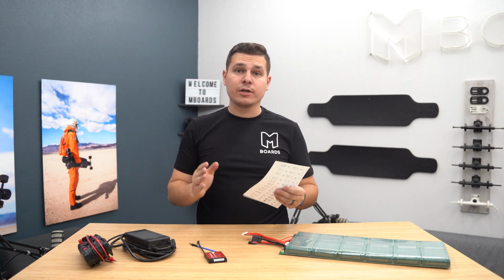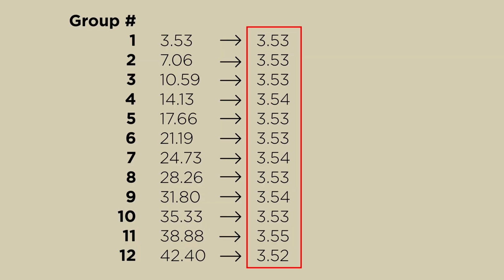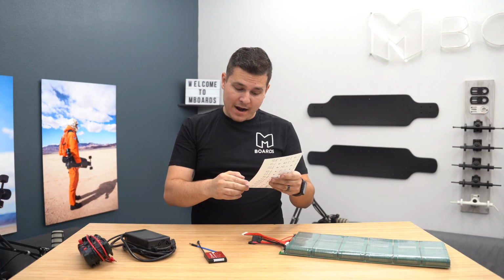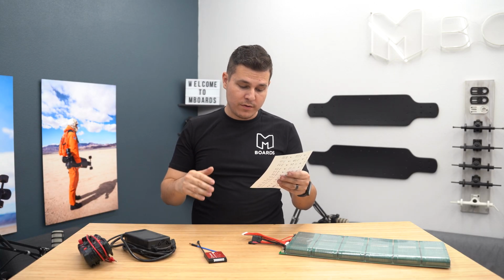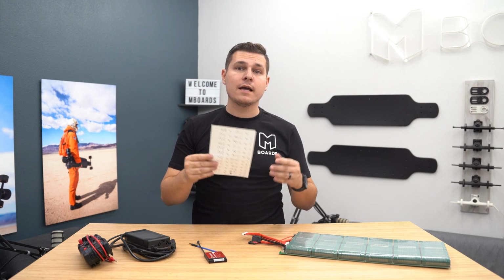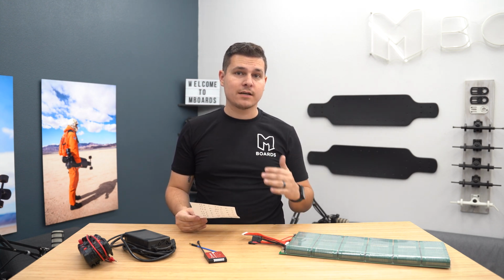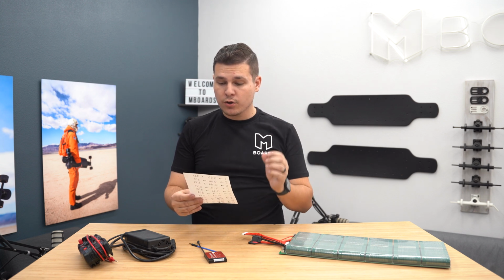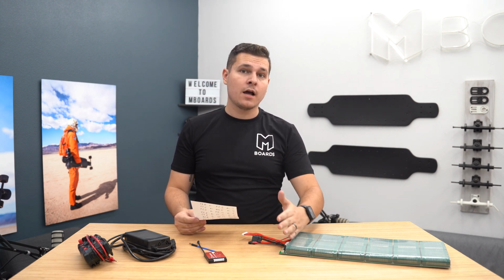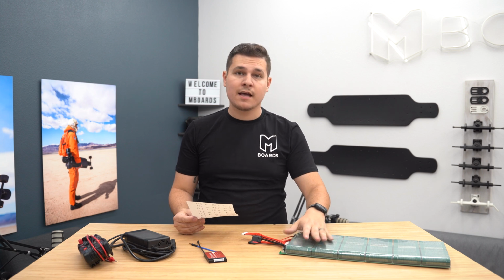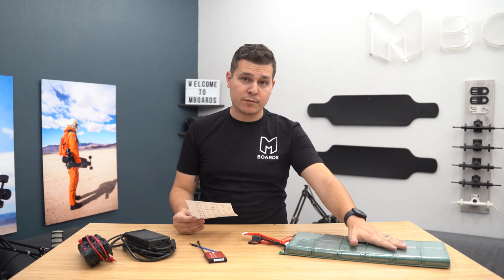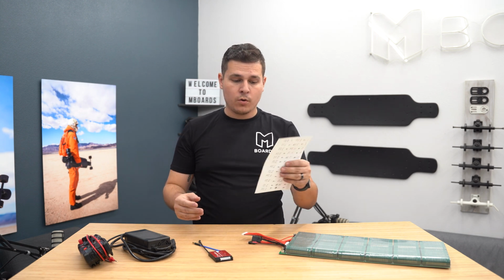So ideally, what you'd love to see is every single number exactly the same. As you can see, I've got 3.53, 3.53, 3.53, 3.54. My highest value is 3.55, my lowest is 3.52, so we've got a 0.03 volt difference between our highest and lowest cell group. That's great, honestly — 0.03 of a volt delta across all the different packs. This is also a brand new pack that's never been charged, so even after it balances out, it should balance even more once you charge it, but that's very good numbers.